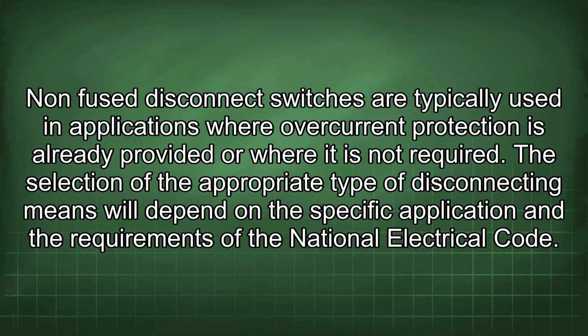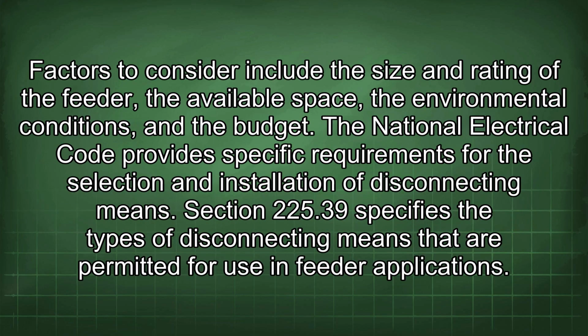The selection of the appropriate type of disconnecting means will depend on the specific application and the requirements of the National Electrical Code. Factors to consider include the size and rating of the feeder, the available space, the environmental conditions, and the budget. The National Electrical Code provides specific requirements for the selection and installation of disconnecting means. Section 225.39 specifies the types of disconnecting means that are permitted for use in feeder applications.